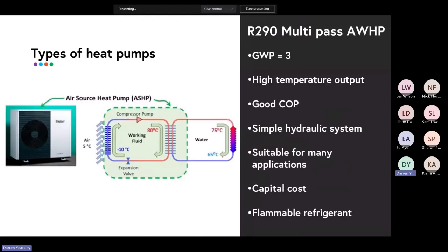So the advantages of your R290, it's got low GWP. So currently score of 3, that might be revised down fairly soon. High temperature output, so it'll reliably put out 75-degree water all day long. So you can have 70 on the return, 75 on the flow. You get very consistent, good COPs. So real world operation, we're getting between 3.5 would be typical. So 1 kilowatt in, 3.5 kilowatts of hot water out.